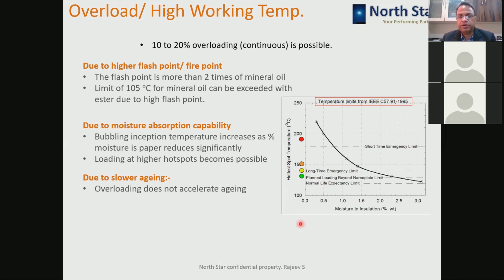So this graph is depicting that when you keep the transformer dry, the bubbling will happen at a temperature of more than 230 degrees centigrade. But if the moisture is high, say 2.5, then bubbling can even start at around 110 or 120 degrees centigrade. And your transformer, you cannot load more than this limit. Okay, so that is the disadvantage when the moisture inside the transformer is high, which is a normal case with mineral oil.